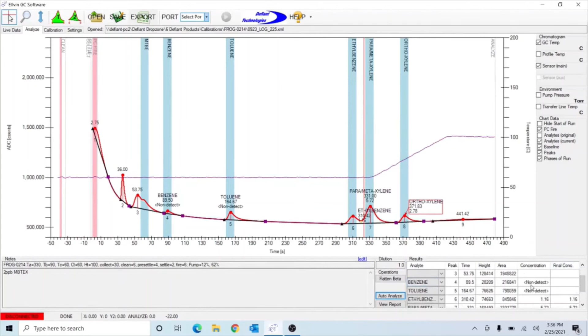After you have entered all 5 calibration points, or however many you're going to do, you're going to go back to the Calibration tab. Now notice that there's 5 for every analyte. That's what you want to see. As I mentioned before, 5 is our preference, but you want to do a minimum of 3 for a linear fit or 4 for a quadratic fit.